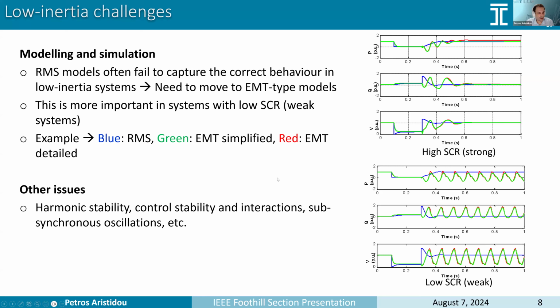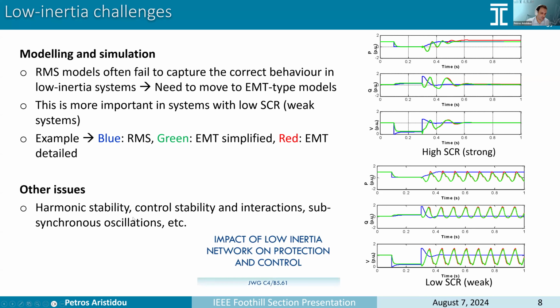There are many other issues that are related to low inertia systems, like harmonic stability, control stability, and control interactions. That's a very big area. Subsynchronous oscillations might show up, as well as problems with transient stability or angle stability. Sometimes in low inertia systems, we have problems with damping torque in the system. But we're not going to go into detail in these areas. There is a CIGRE working group whose final report will hopefully come out by the end of this year, which discusses in more detail the different problems and the different solutions for low inertia networks in protection and control.